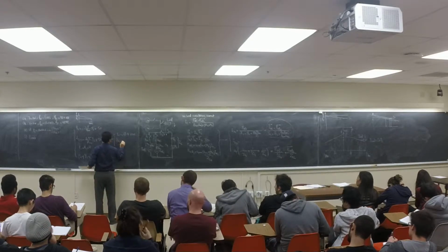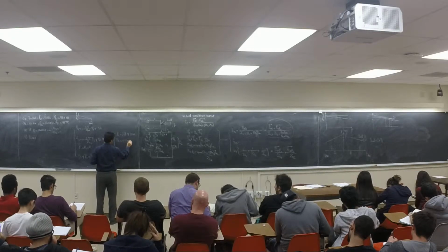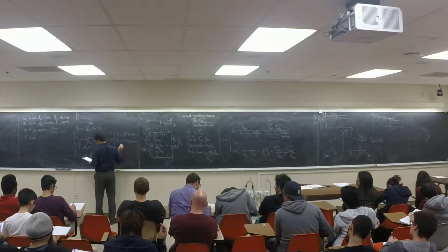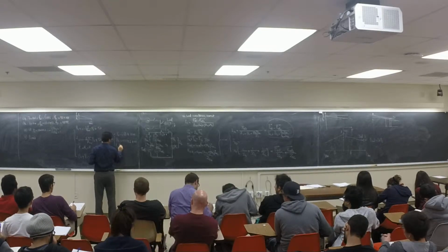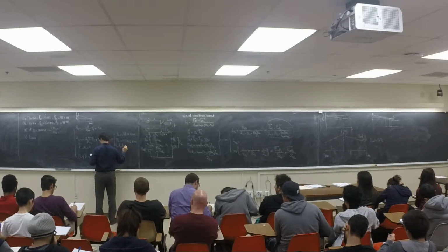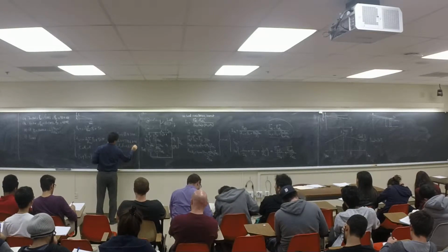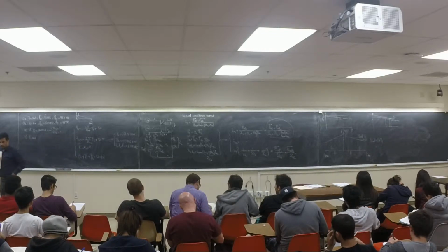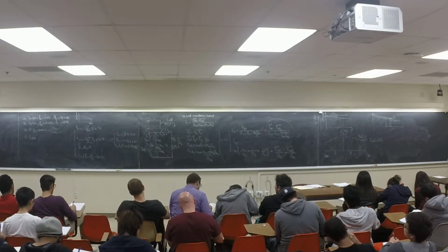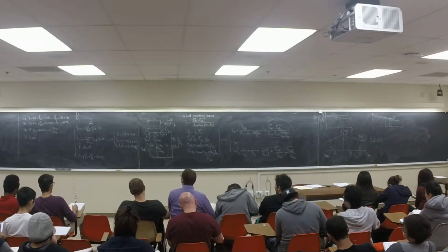P2 is going to be 537.6 kilowatt, and the system is going to work at a frequency of 48.58 hertz. So they're going to share the load like this: one is going to give us 660, the other one is going to give us 540 kilowatt.